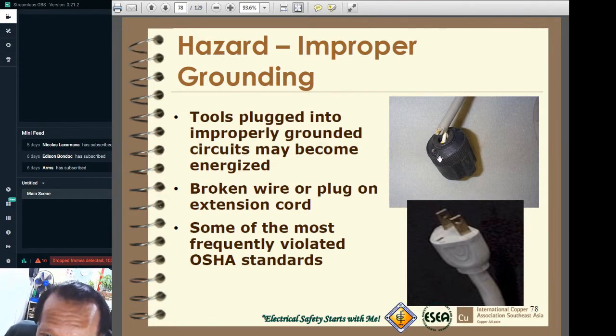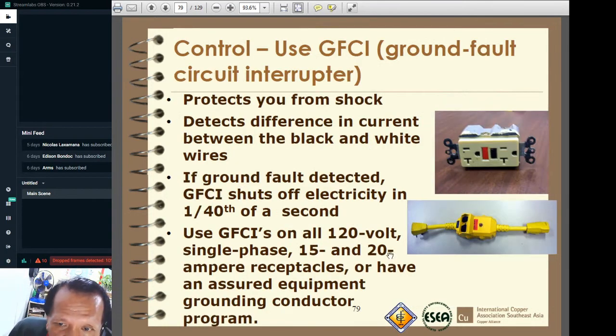What's correct is to provide the grounding in the wire. Okay, and we must use the GFCI. Remember that in the earlier part of this presentation, you have the accident that happened there in Zamboanga, as well as in España, okay, in Sampalo. So the circuit did not provide for a ground fault circuit interrupter, and therefore it created a problem.